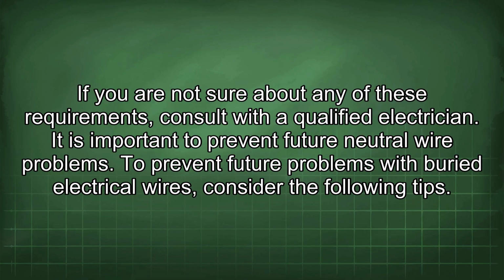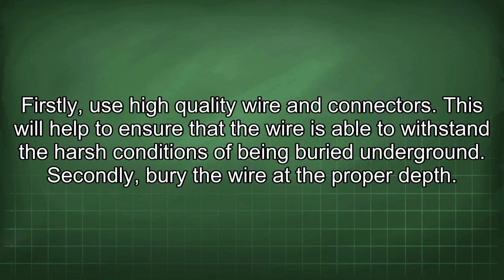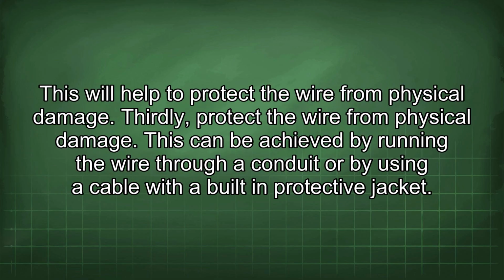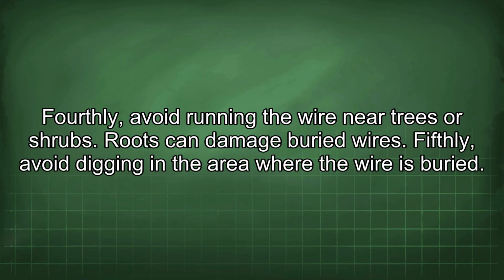To prevent future problems with buried electrical wires, consider the following tips. Firstly, use high-quality wire and connectors. This will help to ensure that the wire is able to withstand the harsh conditions of being buried underground. Secondly, bury the wire at the proper depth. This will help to protect the wire from physical damage. Thirdly, protect the wire from physical damage. This can be achieved by running the wire through a conduit or by using a cable with a built-in protective jacket.